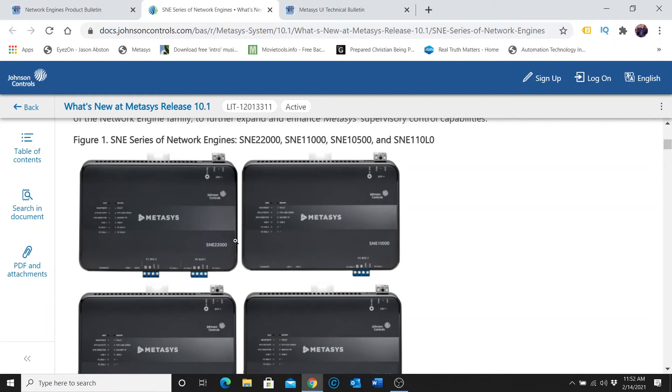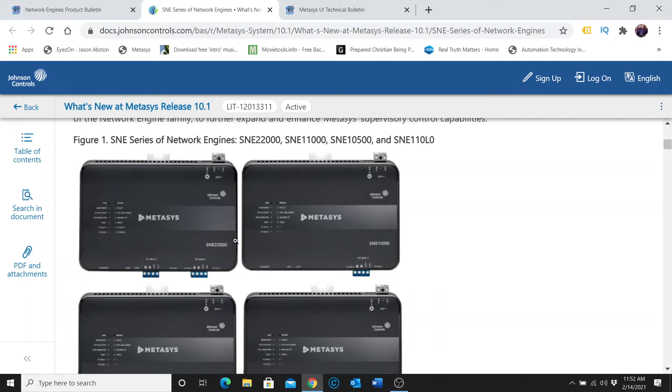you could say that Johnson Controls is going through some growing pains or some trials with some of the technology that is in those currently. From what I'm being told, that it's recommended basically not to go with one of them, but to simply go with an SNE and put a controller underneath it, instead of having a single device that is a network engine as well as a controller.